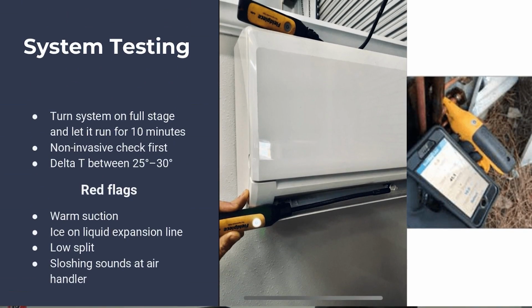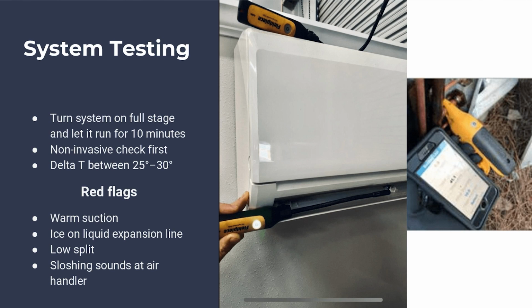Important. Okay, so let's go straight into testing the system. A ductless system that's working well can be tested pretty easily. You're going to want to make sure you turn the unit on at full stage so the compressor is actually running full speed - that's the only way to accurately check your readings.